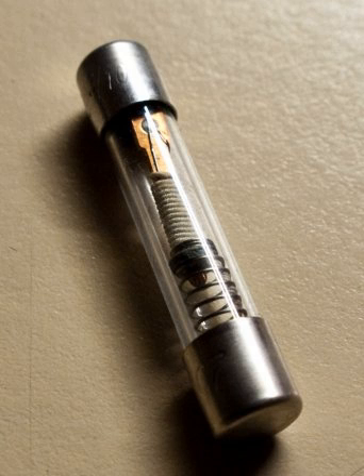High rupturing capacity fuses can be rated to safely interrupt up to 300,000 amperes at 600 volts AC. Special current limiting fuses are applied ahead of some molded case breakers to protect the breakers in low voltage power circuits with high short circuit levels. Current limiting fuses operate so quickly that they limit the total let-through energy that passes into the circuit, helping to protect downstream equipment from damage. These fuses open in less than one cycle of the AC power frequency. Circuit breakers cannot match this speed.